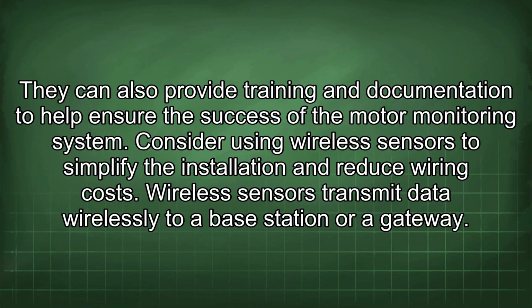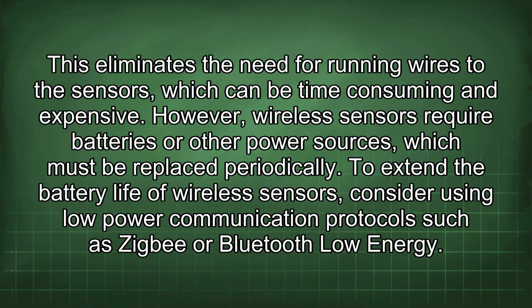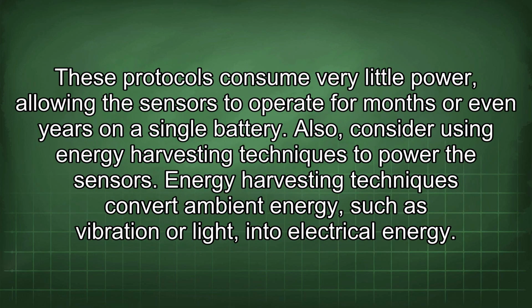Consider using wireless sensors to simplify the installation and reduce wiring costs. Wireless sensors transmit data wirelessly to a base station or a gateway. This eliminates the need for running wires to the sensors, which can be time-consuming and expensive. However, wireless sensors require batteries or other power sources, which must be replaced periodically. To extend the battery life of wireless sensors, consider using low-power communication protocols such as Zigbee or Bluetooth Low Energy. These protocols consume very little power, allowing the sensors to operate for months or even years on a single battery.